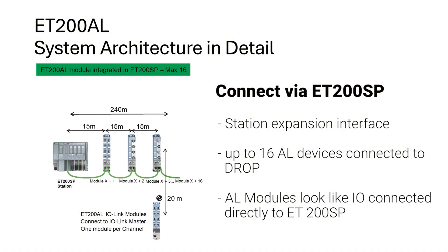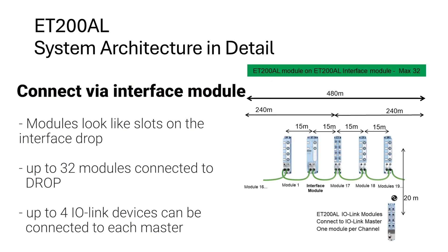The second way to connect the ET200AL is via an interface module connected to the S7-1200. All the modules look like slots on the interface drop. Using this method, up to 32 modules can be attached to the drop. The interface acts as the ET200AL interface to the system.